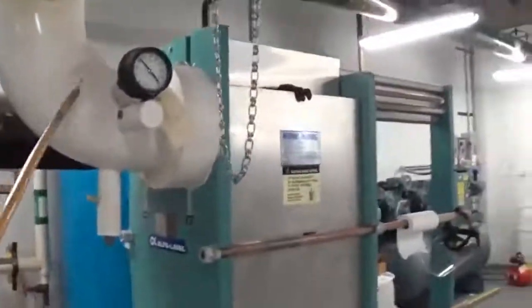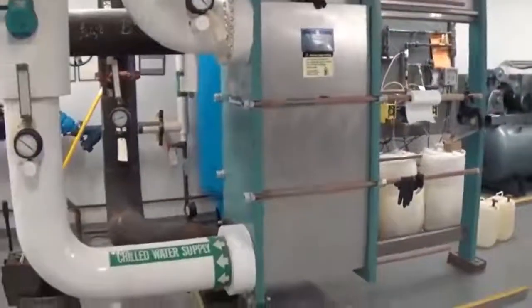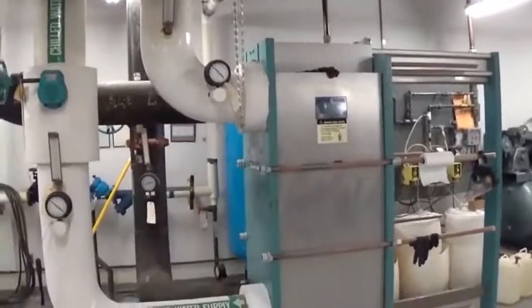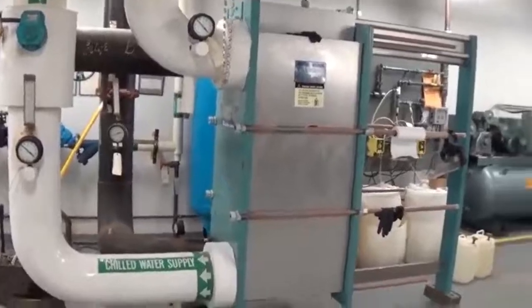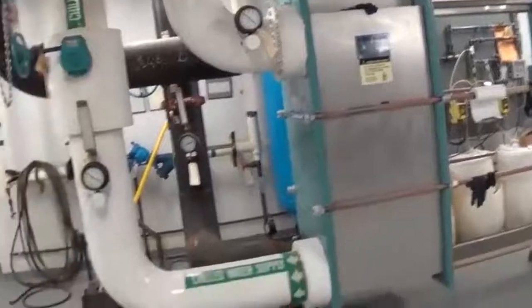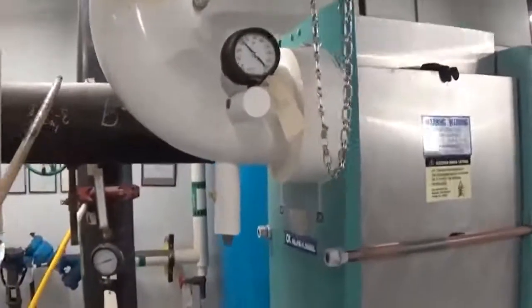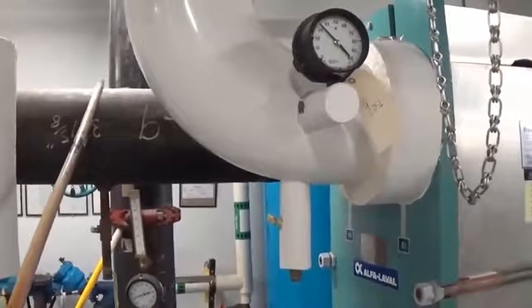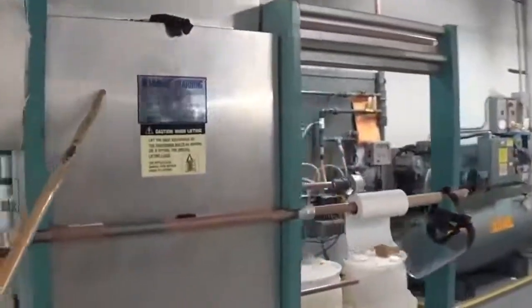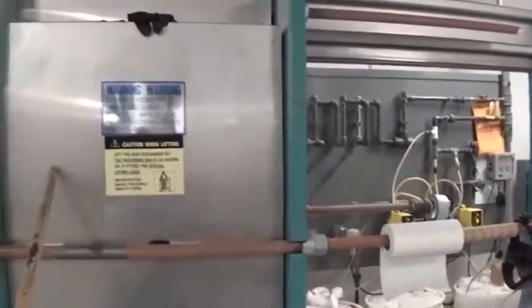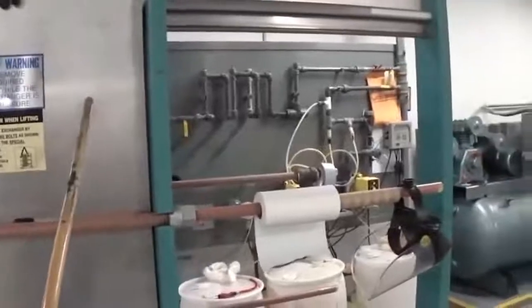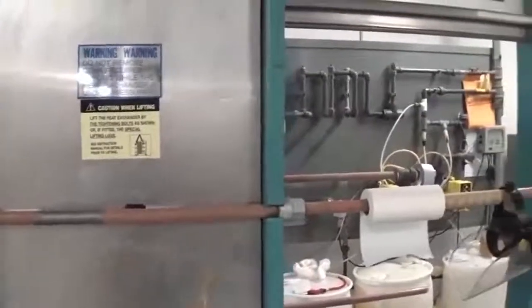Now, this building also has a nice feature with what's called an economizer, and that's what we're looking at now, or a heat exchanger. And what this piece of equipment does, through some sophisticated automation, which is located in the chief building engineer's office, it watches a condition called enthalpy. And when it decides that the outside temperatures and the water in the cooling tower has now become so cold that it can utilize that water for free cooling, it shuts the chiller machines off, captures that water, circulates it through this machine, which is basically just a bunch of copper plates, and migrates the cold water from the outside to the warm building chilled water, which comes in there, and therefore through principles of physics, it takes the cold water and makes free chilled water, courtesy of nature.